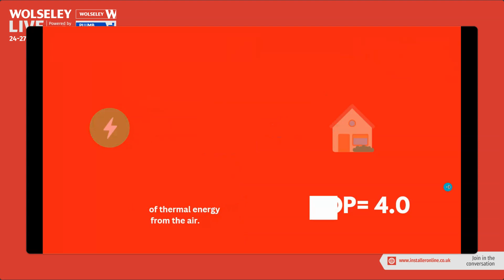In all of our alpha heat pumps, we use R32, the refrigeration gas. It's pretty well-known across the industry, a lot of manufacturers use it, and it's quite environmentally friendly. The fundamental bit is that R32 has a boiling point of -51 degrees, so at outside normal temperature, even on a chilly day, that is absolutely boiling.